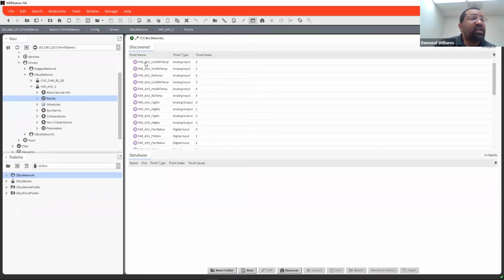Right now, as you can see, this controller right here was a controller that was donated to us from University of Houston. The way the system was set up is the building initials, what air handler it was, and then what the point name was. So as you can see, I have air handler 1, I have air handler 3 in here as well, and a bunch of other points. So they even show some of the statuses of the controller itself, its startup status, shutdown status, and then if it's executing a stop or anything like that. So it does pull all of that information out as well.